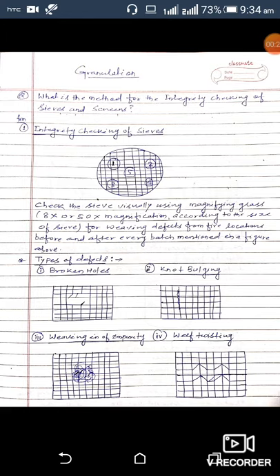Check the sieve visually using a magnifying glass at 8x or 50x magnification, according to the size of the sieve, for weaving defects — from five locations before and after every batch, as mentioned in the figure above. In that figure I have located five points from which we check the sieve for integrity.